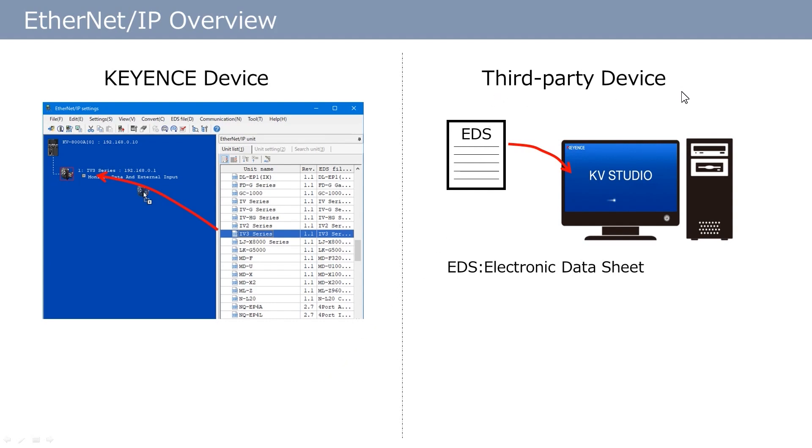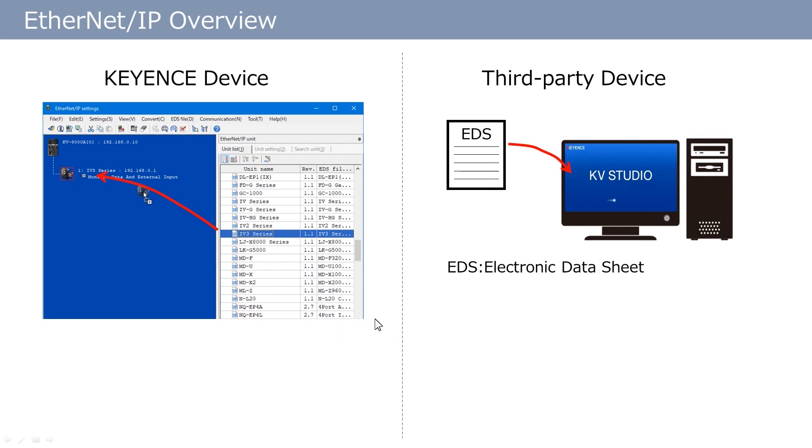Even adding units from other manufacturers is possible by selecting it if the EDS file is registered. An EDS file contains the settings and information necessary for Ethernet IP communication. When the EDS file is registered, the file is displayed in this list with the Keyence units. Now, communication becomes available just by dragging and dropping. EDS files are available from the unit manufacturer's website.